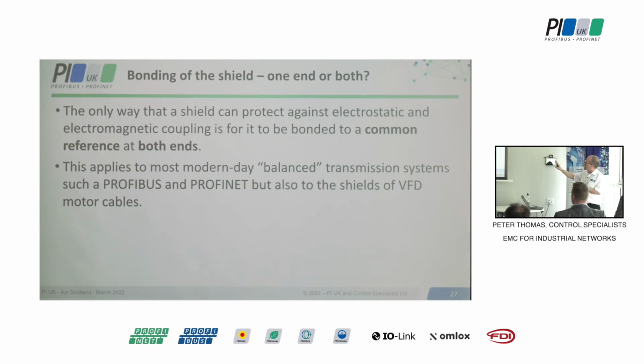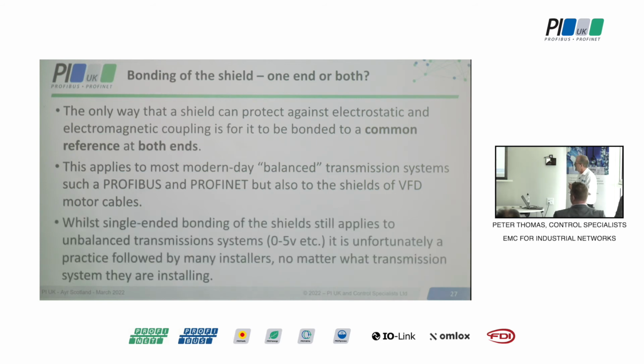And that applies to most modern day balanced transmission systems. What we mean by a balanced transmission system is that every conductor in the cable has got some signal on it. You are not going to be grounding any of those internal conductors. Now, single-ended shielding, in other words, grounding or earthing at one end, still has its place, but it's primarily for unbalanced systems, where one wire is at 0 volts or a ground that you will literally connect to ground, and then there is a signal relative to that. That's still applicable, because if we do bond at both ends with this, we get an earth loop. Unfortunately, it's a practice followed by many installers.